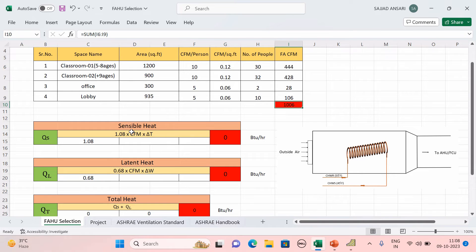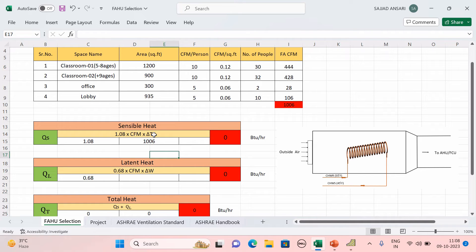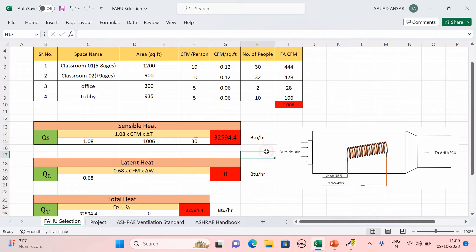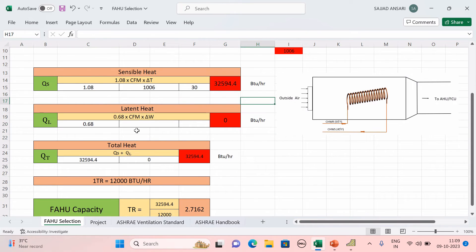Now calculate the sensible heat using the formula: 1.08 × CFM × ΔT. The fresh air CFM is 1006. Delta T is the temperature difference: outside maximum is 106°F for Hyderabad, and inside we maintain 76°F for human comfort. So ΔT = 106 − 76 = 30. This gives sensible heat = 32,594.4 BTU/hr.